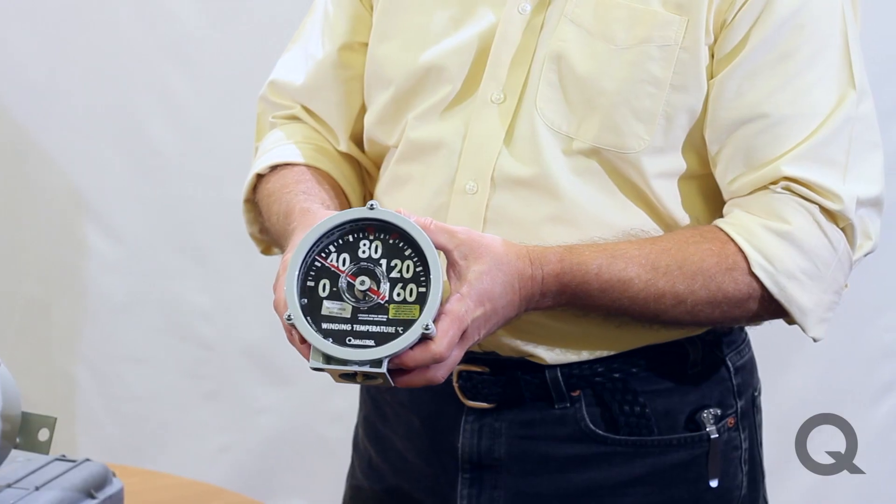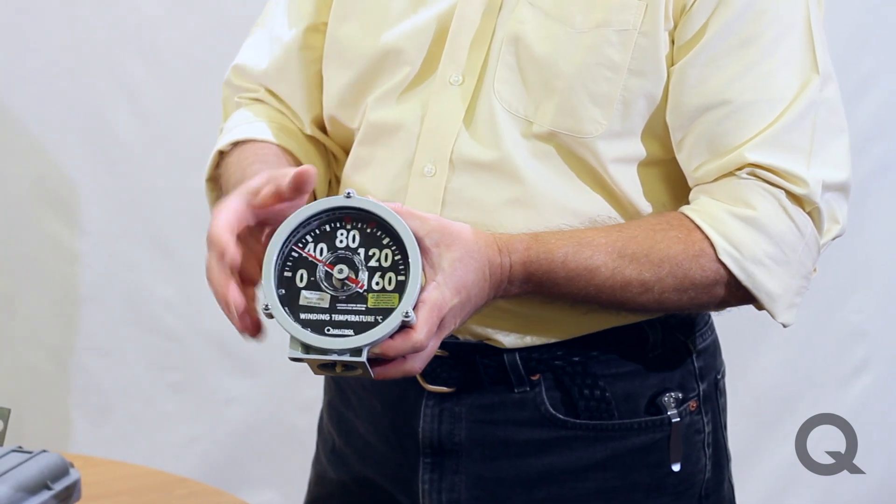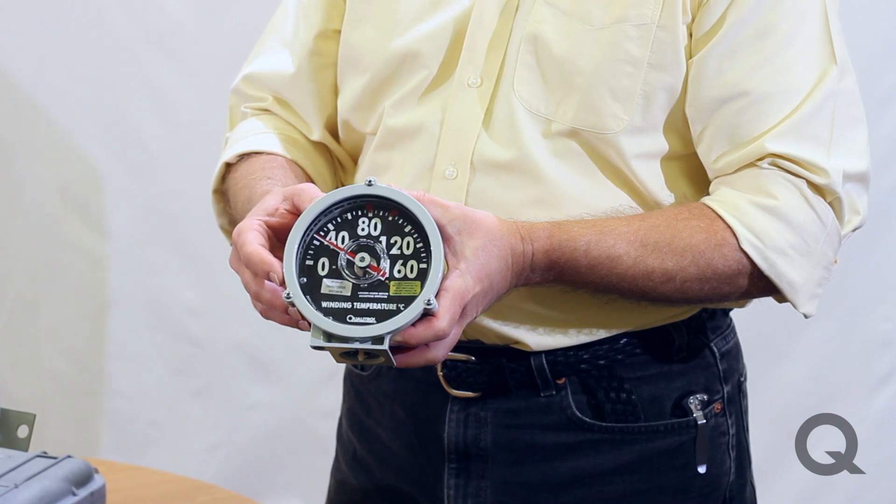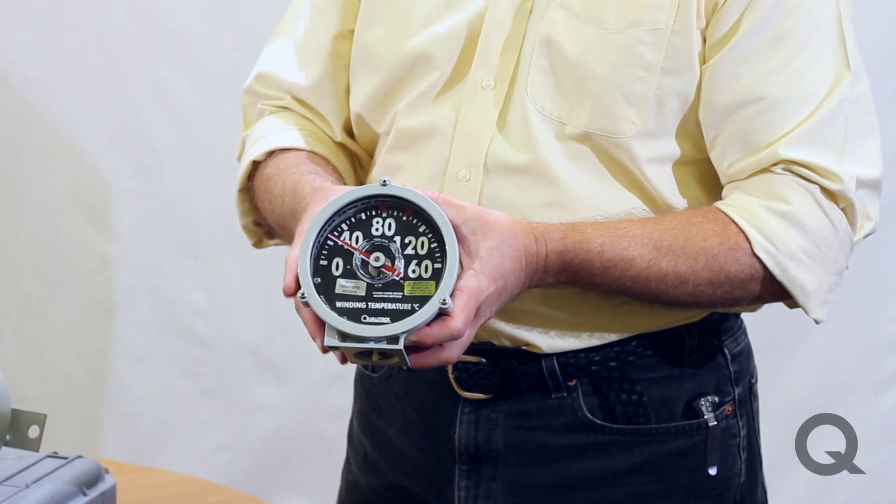The dial range is going to be important. Some winding temperatures will run zero to 160, some will run zero to 220. Liquid temperatures will run zero to 120, typically.